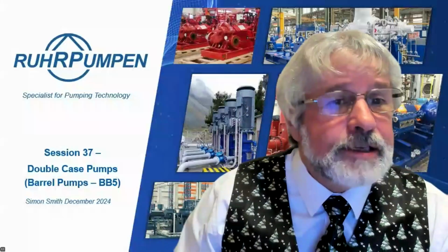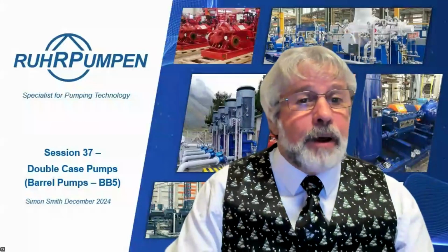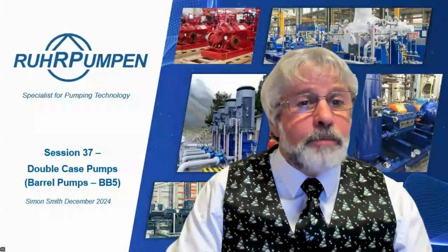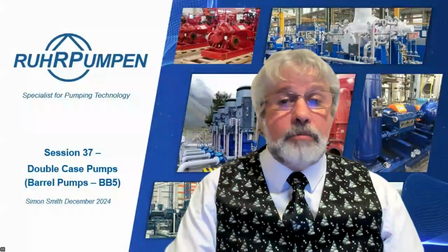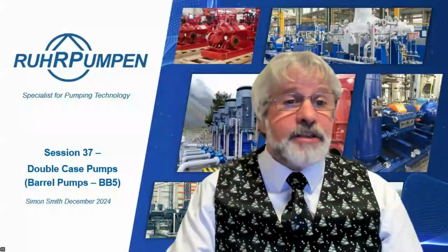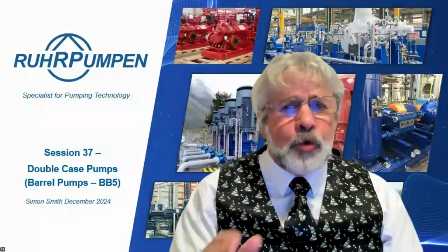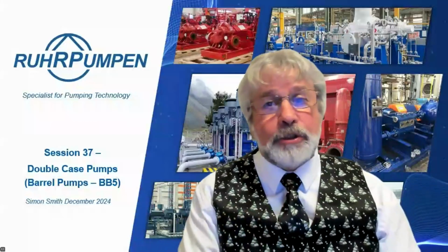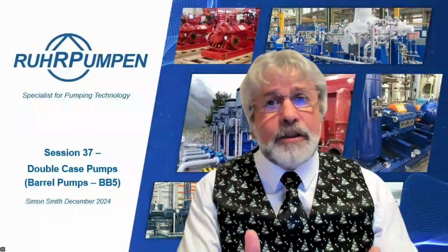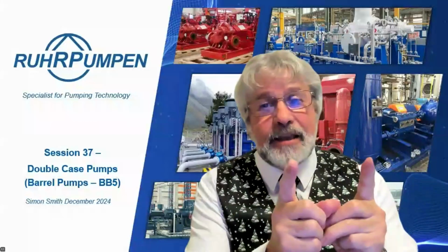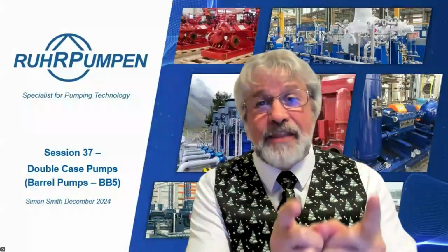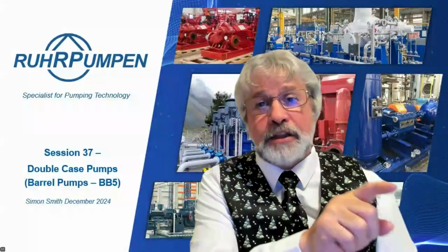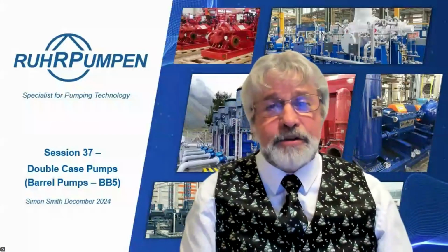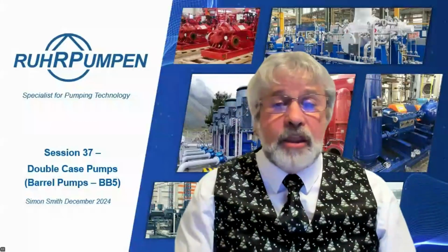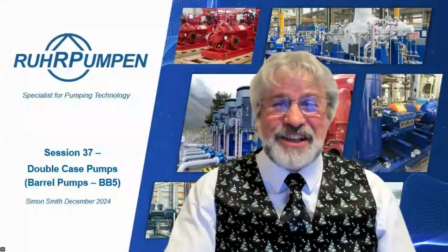Anonymous attendee says, if you have dummy impellers in a pump, does it create thrust-bearing problems that need to be considered? No, because it would have been designed in that case. We don't actually put dummy impellers. What we will do is take out, say, 2 impellers and put a spacer of the same dimension in there instead. So the flow goes directly from one impeller to the next one. So no, is the short answer.